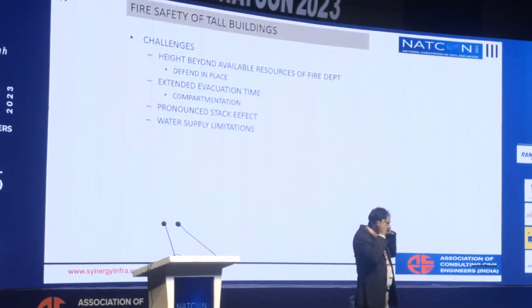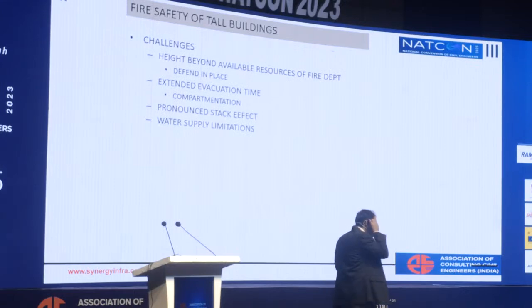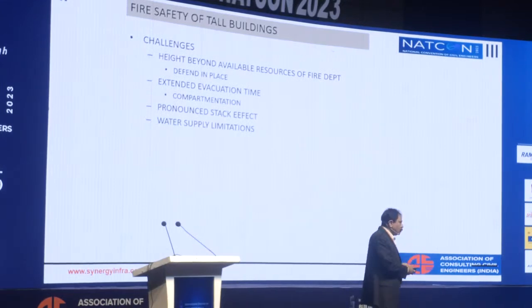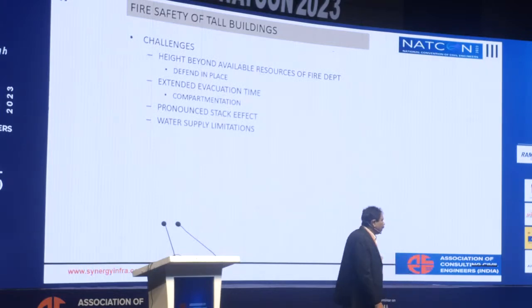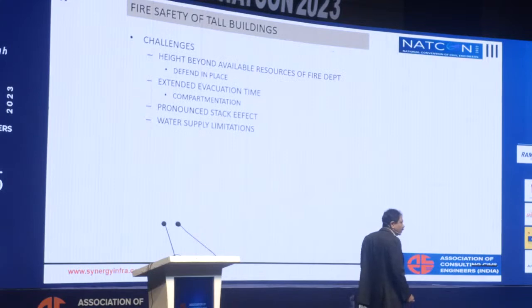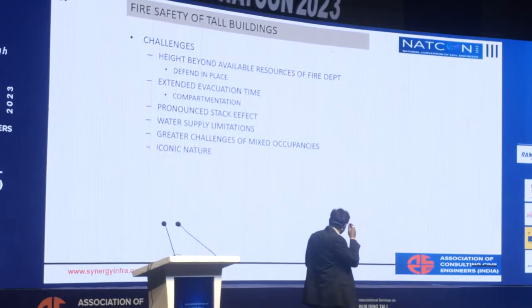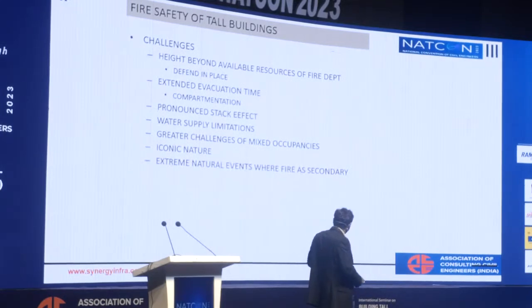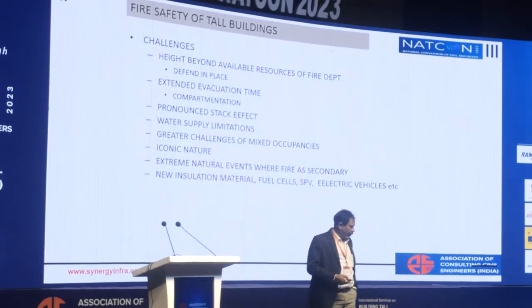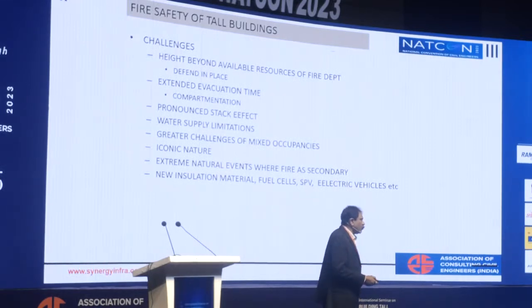Stack effect is one of the major issues in smoke management systems, because depending on the temperature outside versus the fire temperature inside, the air may not go out. Even when you try to open windows, air can come from outside to inside because of the pressure differential caused by the stack effect. That's why we need mechanical ventilation fans, which require power supply in all such cases. There are also water supply limitations, greater challenges with mixed occupancies, buildings that may be iconic, and extreme natural events where fire is secondary but a lot of fuel is being added to many of these buildings today.